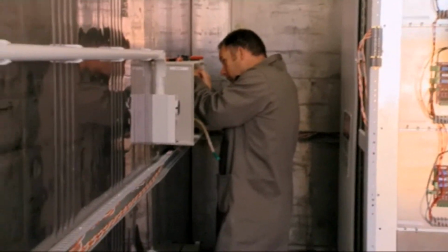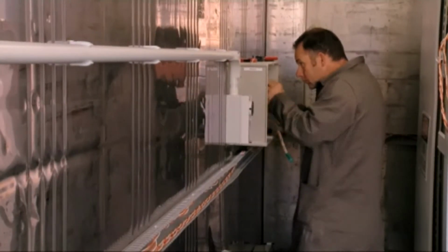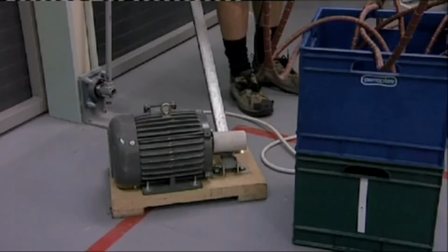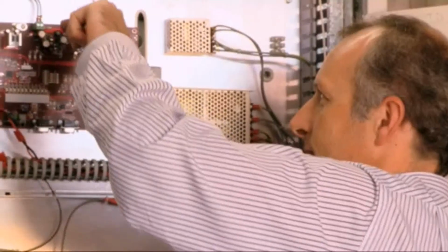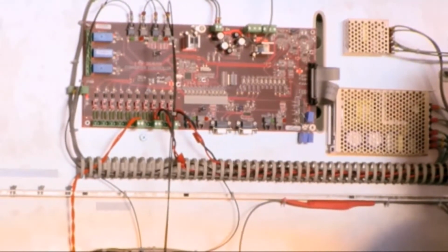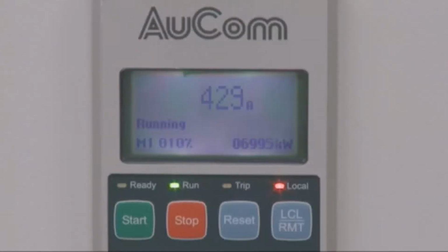So during the commissioning phase, your starter can be connected to a low voltage motor for testing the soft starter and its associated power and control circuits. As well as comprehensive run simulations, the MVX can simulate each protection to ensure the starter is signaling as expected and interacting correctly with associated equipment.